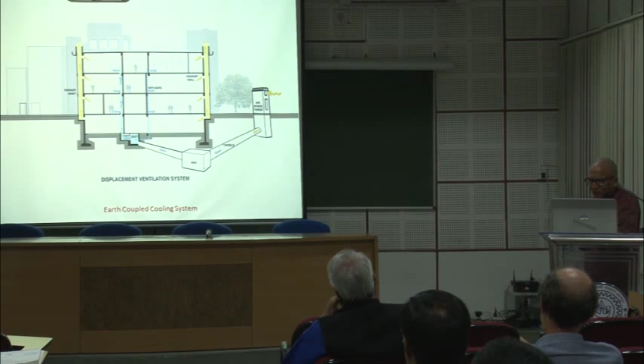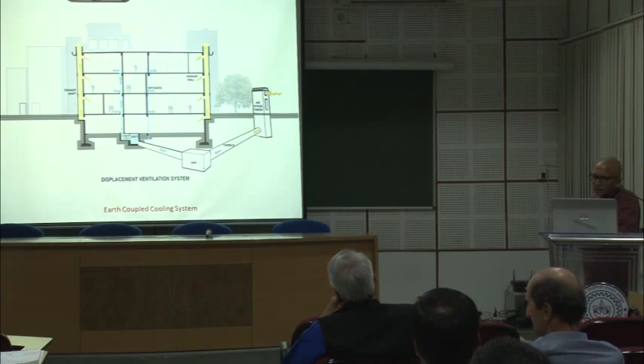The effect of this kind of system here was that dust control is required in Neemrana, and it is not just a question of cooling the building, it is also a question of dust control. So these buildings were supplied with 100% fresh air all the time, with an air washer in the air handling unit, so the dust was never there. It is actually a very good method of dust control in the buildings, and they don't have to clean them as much, but there is a humidity problem here.